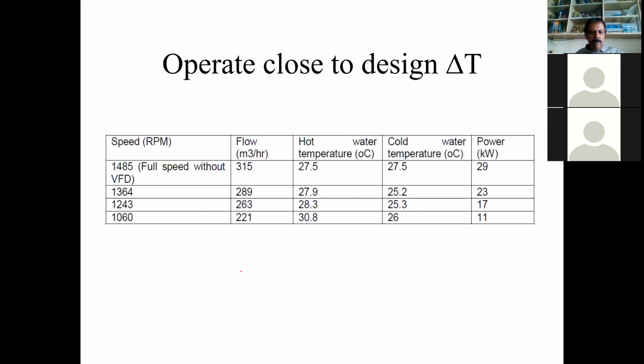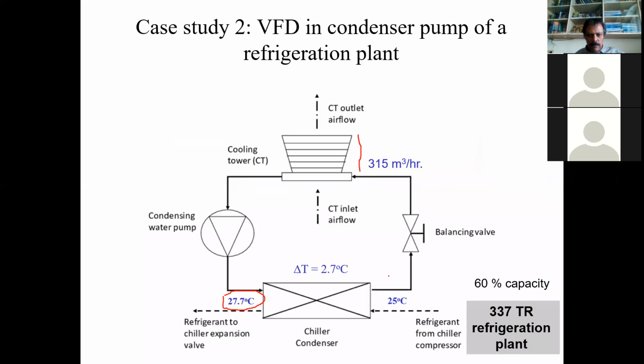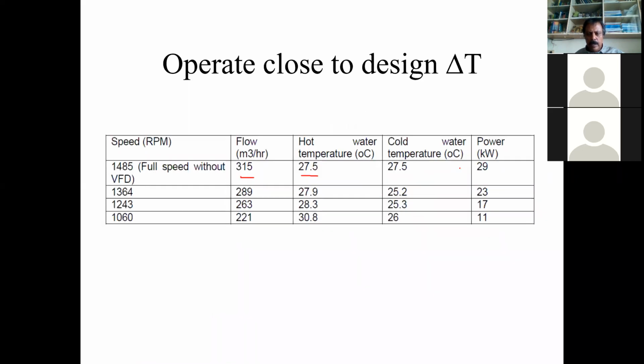Now we have a VFD for this pump. So we operate this pump at different speeds, 1485. At 315 meter cube per hour it is operating. This is the hot water temperature, and this is the cold water temperature. Okay, so this one is 25 and 27.7. And the power drawn for this speed is 29 kilowatt.